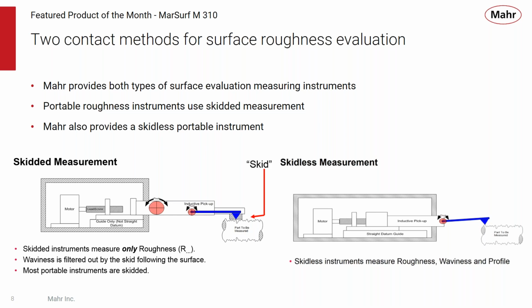Now, a skidless measuring instrument works a little bit differently, and it can be more precise and provide roughness, waviness, and profile information. See, with a skidless system, the reference, which the skid passes over, is based in the drive. And now the stylus runs over the part, and it'll measure the roughness, the waviness, and the profile, and we can pull out all that information. So a skidless measuring system can provide a lot more detail, a lot more information, and usually can perform some higher resolution measuring results.